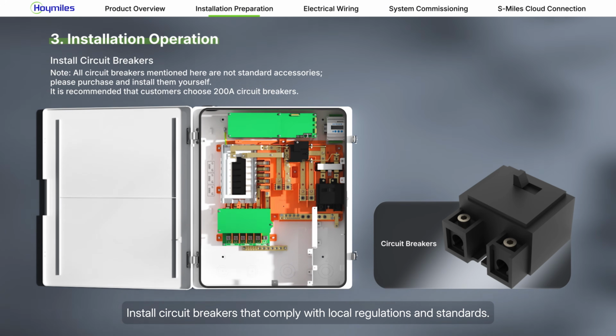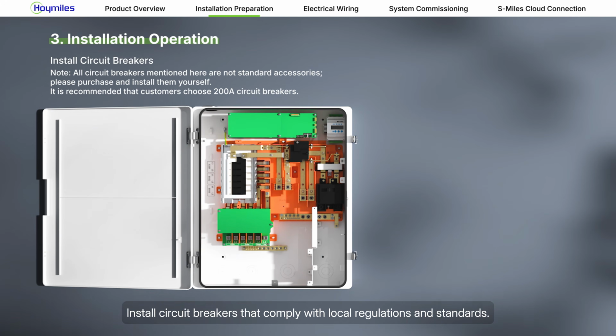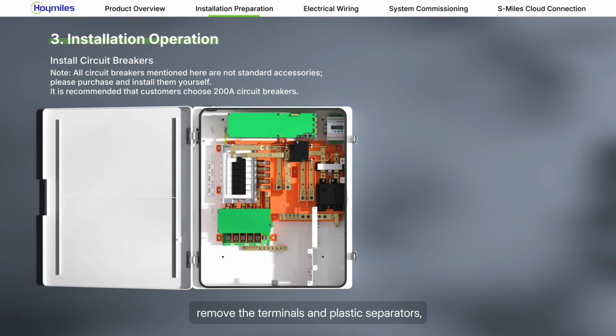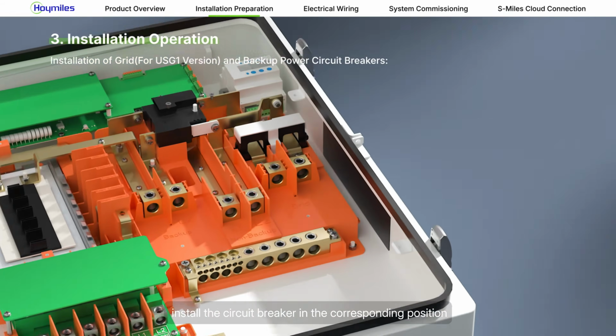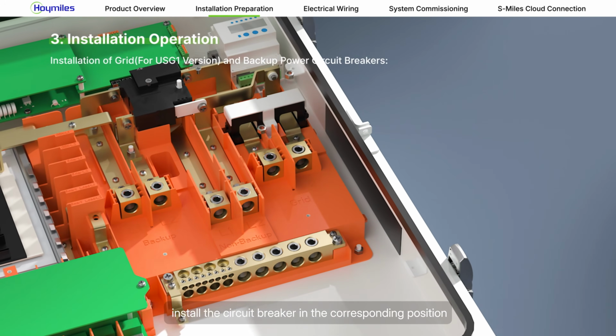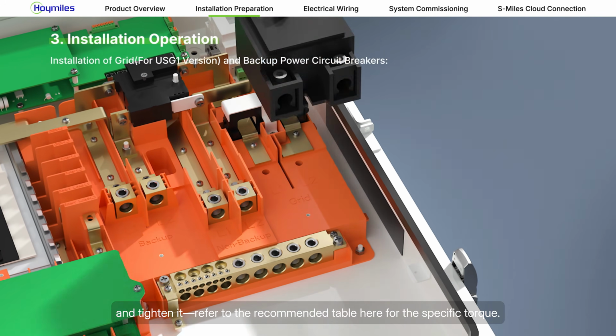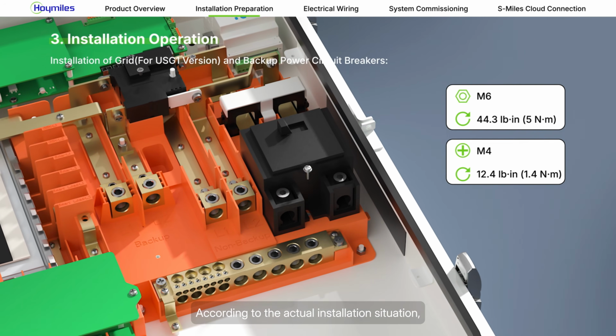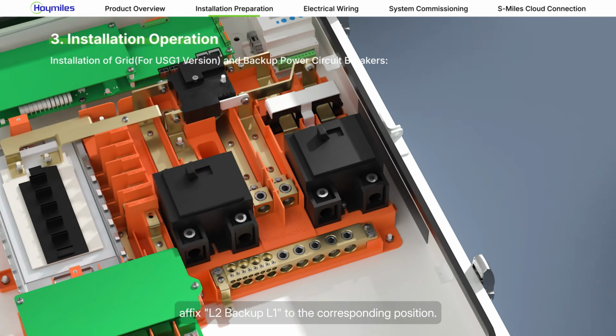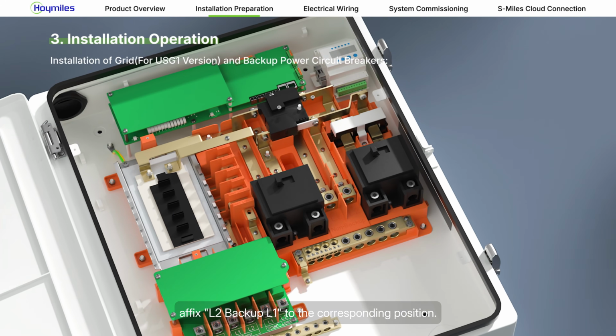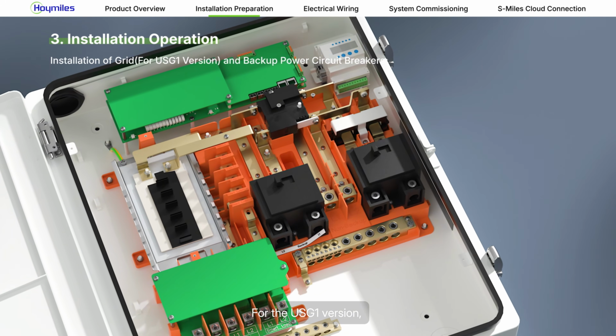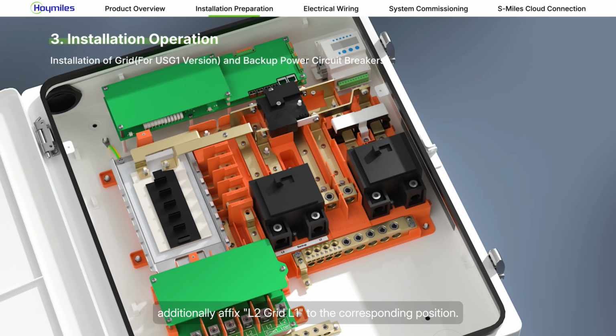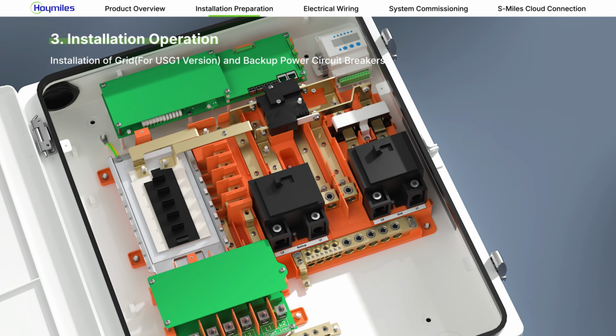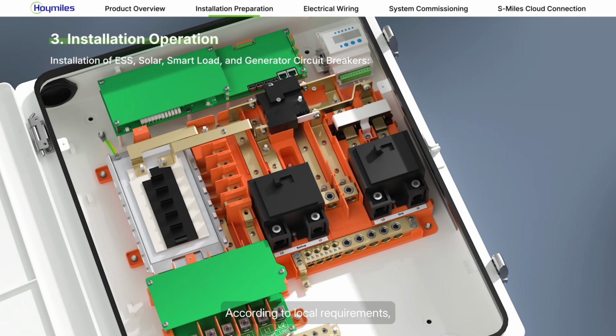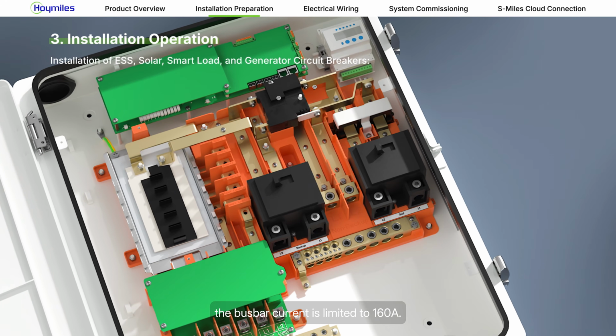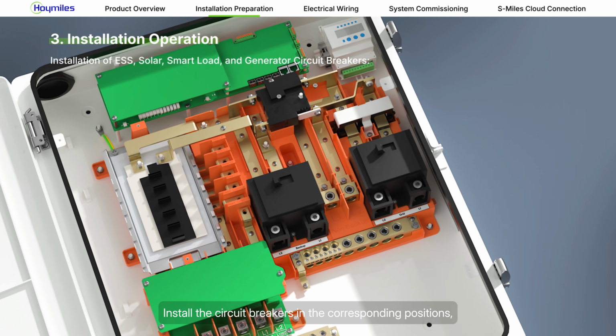Install circuit breakers that comply with local regulations and standards. Loosen the fixing screws, remove the terminals and plastic separators, install the circuit breaker in the corresponding position, and tighten it. Refer to the recommended table here for the specific torque. According to the actual installation situation, affix the L2 Backup L1 label to the corresponding position. For the USG1 version, additionally affix the L2 Grid L1 label to the corresponding position. According to local requirements, the busbar current is limited to 160A.